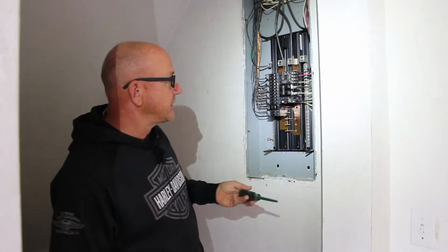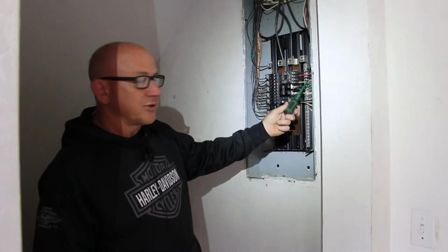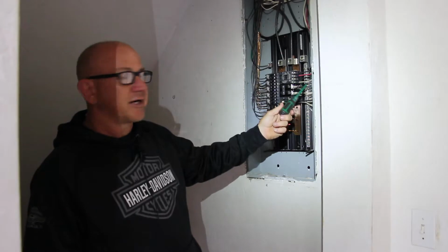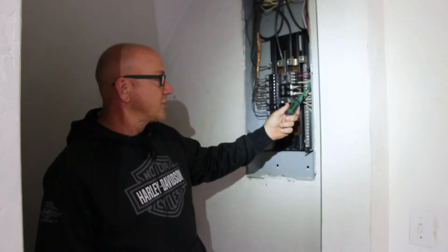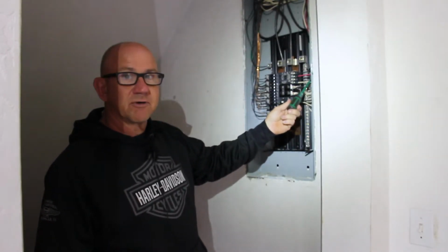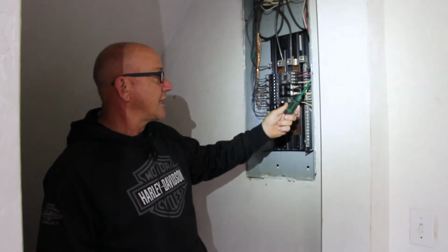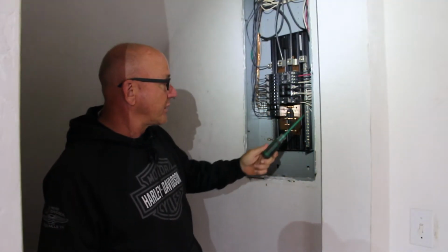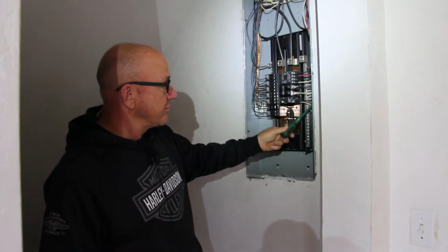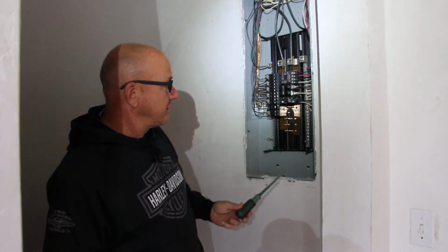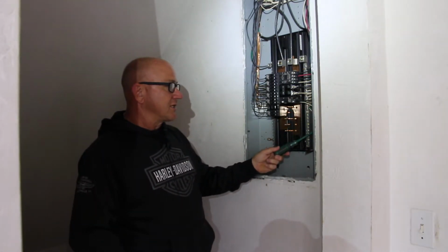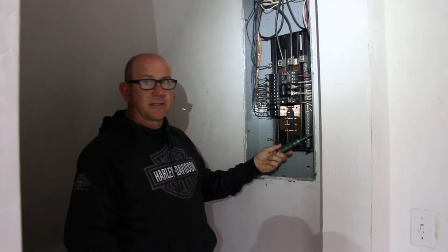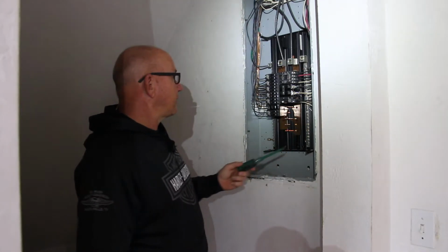One of the problems that we see here is that we have some current carrying conductors that are not identified with black tape or black stripes on them. These are 220 volt circuits, and they should be identified as black, even though they're on white wires. We do have one here that's identified. We have a wire splice inside the panel. That's technically okay. There's no issues with that.